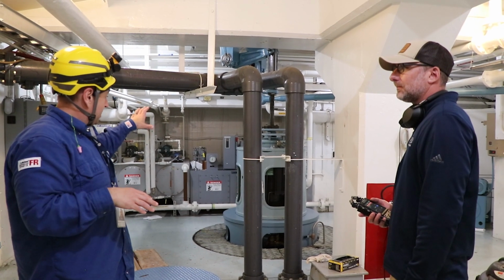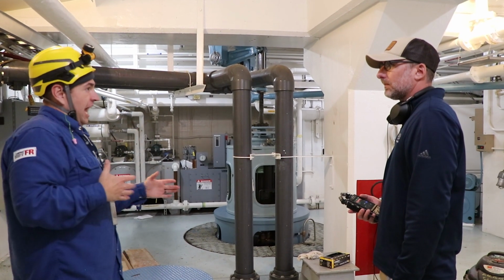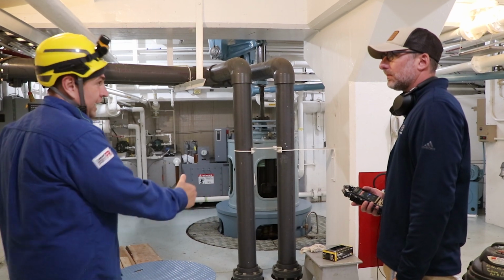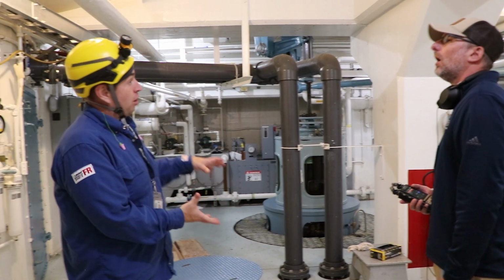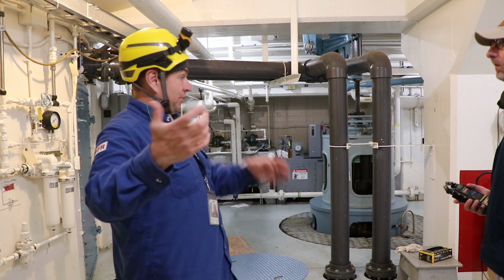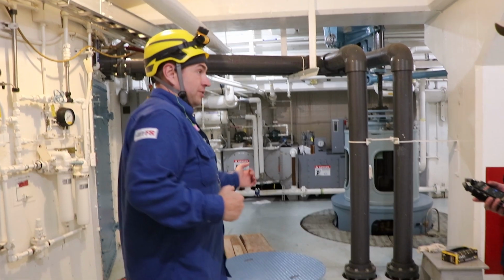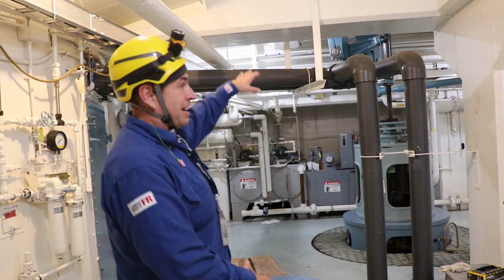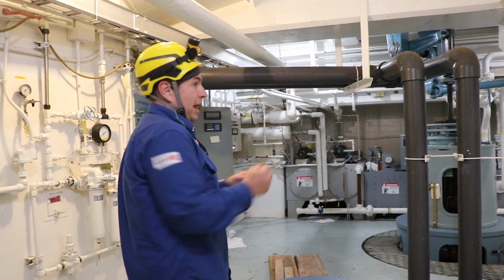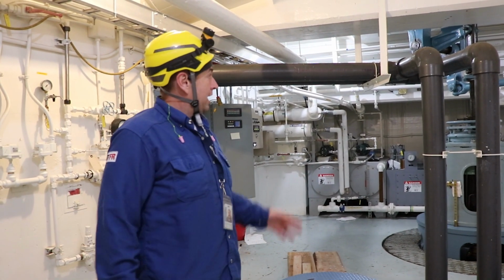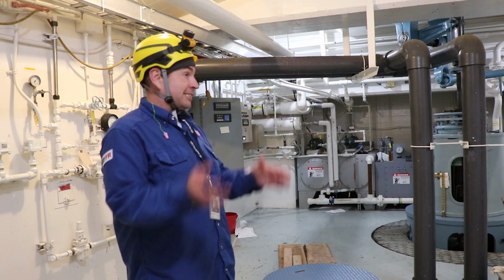Can you talk about how all that connects to the bulk electric system, from the generator to the transmission network? Yeah, sure. So let's start at Ross. Ross is the top of the system. At 60 hertz, we generate electricity at each of the generators. That comes out at 13.8 kV. There's a breaker that connects it to the bulk electrical system, and then from there it's stepped up to 240, and that brings it down the R1 and R2 transmission lines from Ross to the Diablo substation.